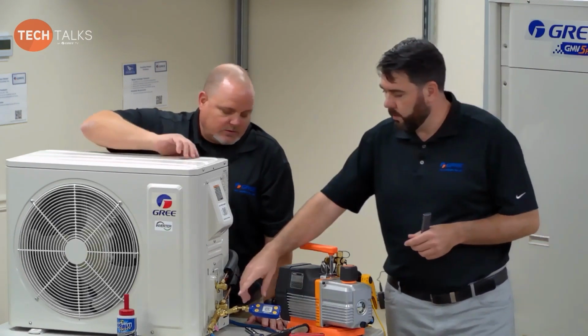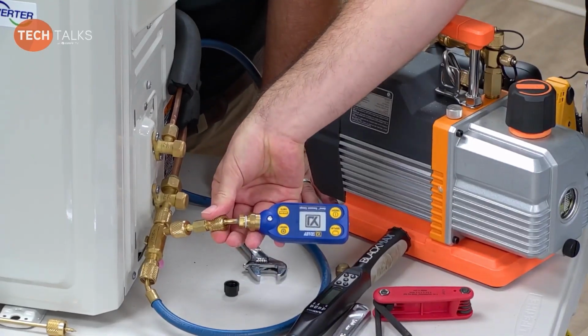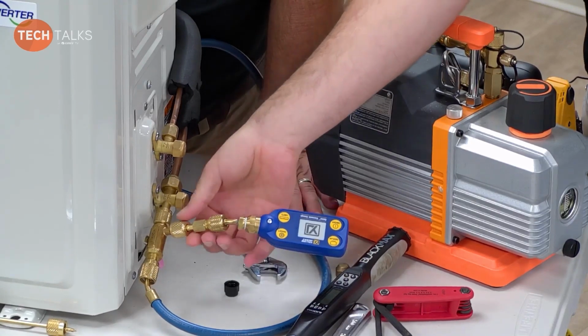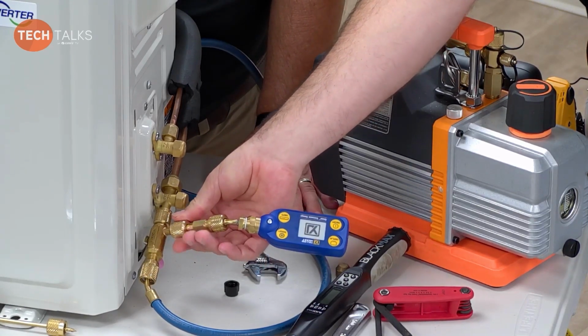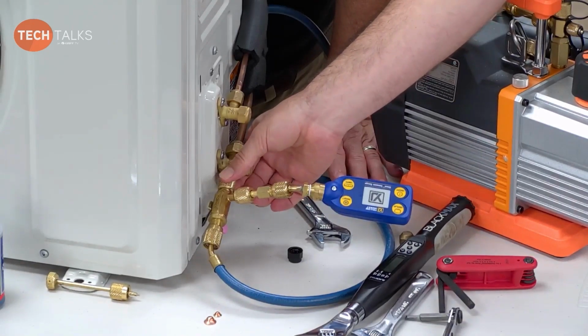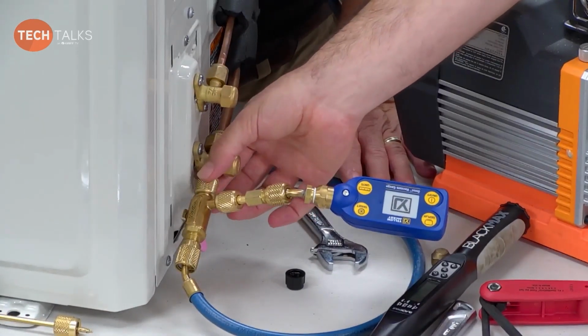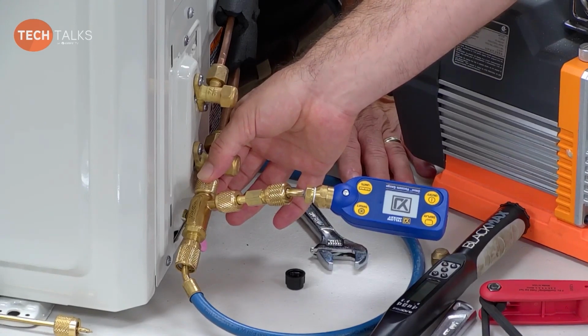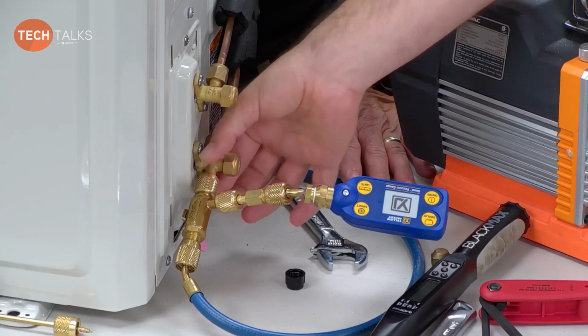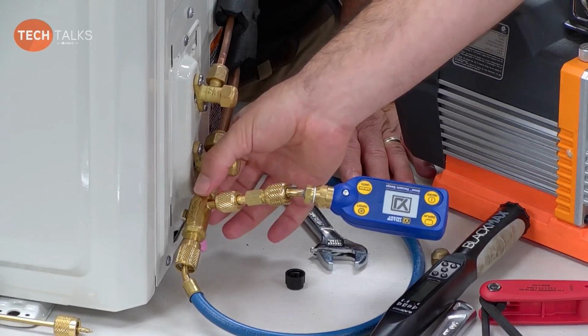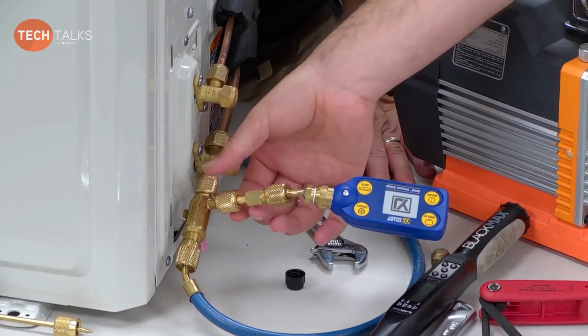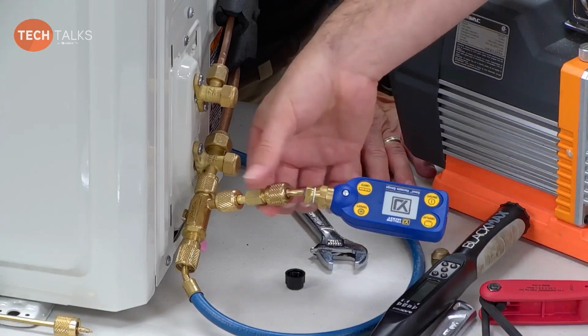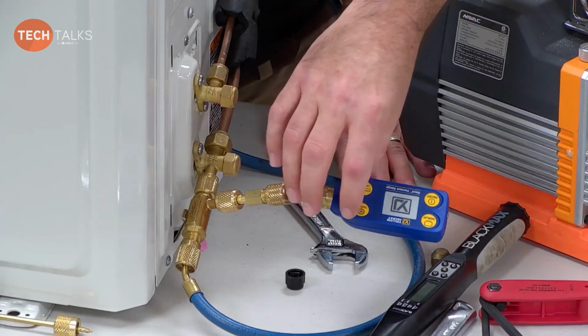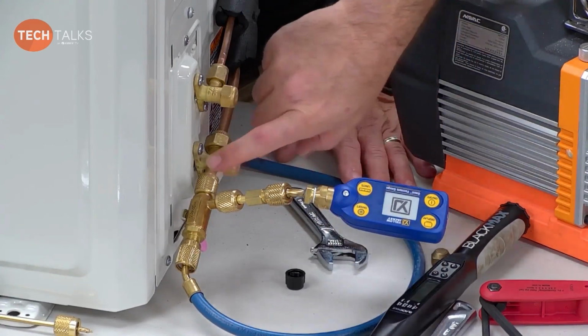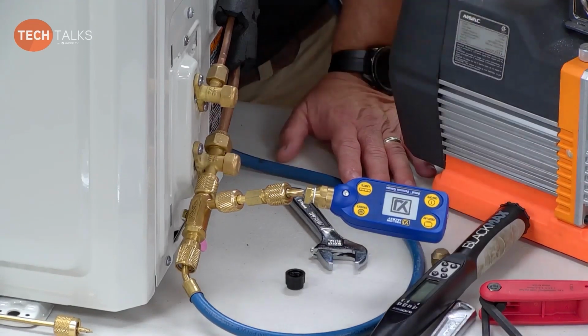Now, this is just the vacuum gauge that I've got, or micron gauge. I've got an adapter because of the Schrader core remover that we have on here. Now, the Schrader core remover is not necessary. We don't have to have that. The only reason I use it in this instance is so that I have a T-port for my micron gauge. I want my micron gauge to be as close to the unit as I can get it. I don't want it to be near my vacuum pump if possible.